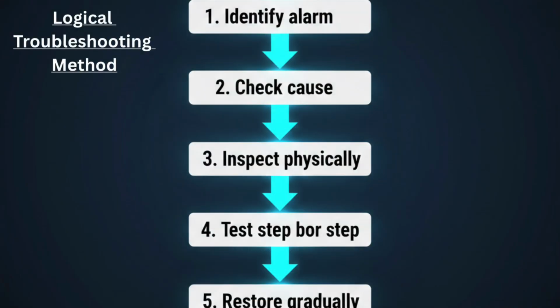Logical troubleshooting method. Now let's summarize the correct troubleshooting approach. Step 1. Identify alarm clearly. Step 2. Understand trip cause. Step 3. Check meters and logs. Step 4. Inspect physically. Step 5. Test step by step. Step 6. Restore gradually. Never guess. Never reset blindly. Never bypass protection without understanding risk. Good engineers use logic and patience. Documentation also helps. Record what happened and what action was taken. This systematic approach builds professional confidence.